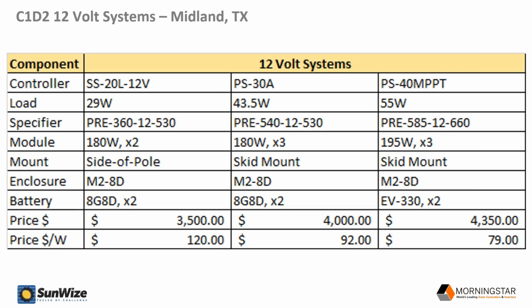At the bottom, you'll see the first two systems are using the MK Deka 8G8D batteries. But as the load goes up for that third system at 55 watts, we have to make a couple adjustments in order to get that minimum 5 days of autonomy, namely going from the 8G8D up to the EV330 battery, which gives us quite a bit more capacity on a per battery basis using the same form factor.